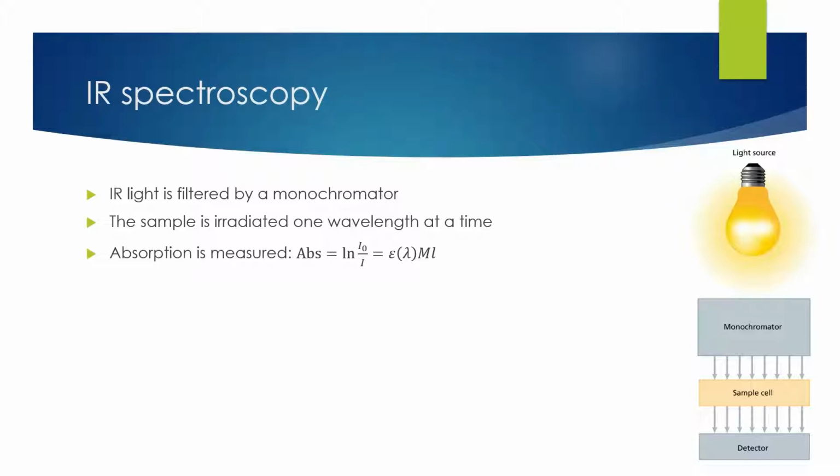As we've already seen in some of our labs, if we have too much sample, we'll absorb all of the light, and that's not going to give us an accurate measure of what's going on because we've absorbed all the light and we haven't actually probed how much stuff we have. And for this reason, spectroscopy is limited, and there's what's called a linear range in the instrument where Beer's law applies. Outside of that linear range at very dilute or very concentrated samples, you start to mess with this and you start to absorb too few photons or too many photons, and your accuracy is diminished. So you need to know the linear range of your instrument if you actually want to get accurate readings.